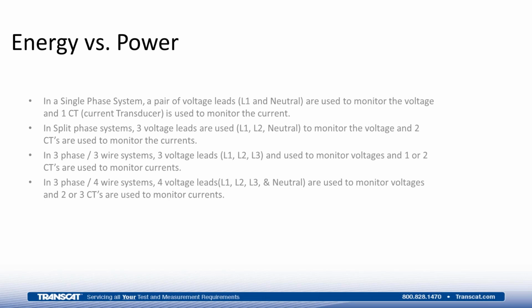And then you would have to have some type of device, which we call a current transducer, which would wrap around only one of those conductors. Then we would be able to monitor the current and the voltage, and products can then calculate the wattage from the voltage and current being monitored. That would be characteristic of a single-phase system. And our residential structures are based on a pair of single-phase systems. In our residential structures, we have what is called a split-phase system.